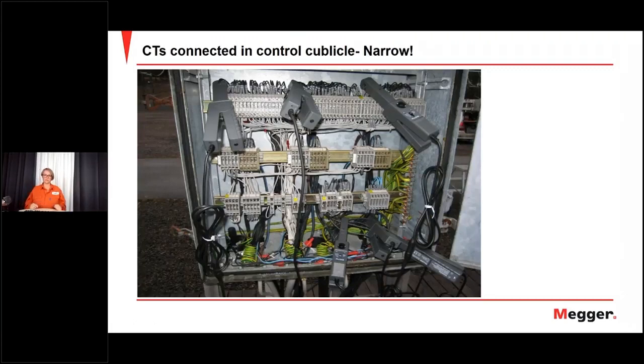Here you can see that it can be a bit tricky here, even just to get them connected. The cubicle may be big enough, but the terminals here are quite small, so it gets quite narrow. It's a nicely built cubicle, but a bit narrow for our testing work to be done. So we have three currents for the controls and three current clamps for the CTs.